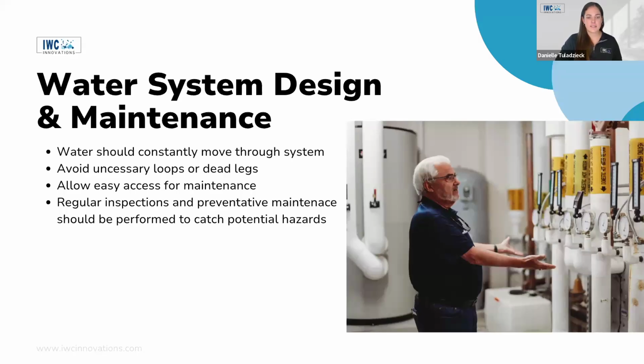Once a system's in place, consistent inspections and preventative maintenance help catch potential issues like corrosion, biofilm buildup, and failing components, all before they become health hazards. If your building makes system modifications during renovation projects, it's important to always consider how those changes are going to affect the system design and the flow of water. Remove any unused piping—even just a few inches can harbor Legionella.